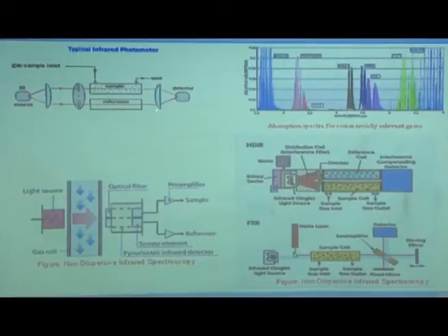Okay. So, what happens is that in the reference gas you have a gas composition which is very similar to the exhaust gas minus the carbon monoxide. That means there will be no carbon monoxide here. In the sample gas there is carbon monoxide, it is passing.